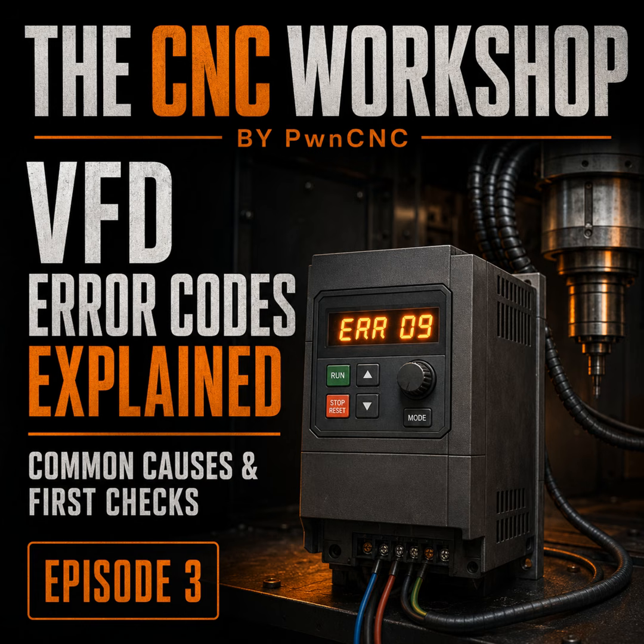Daniel, if listeners remember just 3 things from this episode, what should they be? First, an error code is a clue, not a complete diagnosis. Second, if the spindle stops during a cut, stop the CNC and do not repeatedly reset the VFD. Third, preserve the evidence, photograph the display, record what the machine was doing, and inspect the system safely before anything gets rebooted or changed. That alone should prevent a lot of damaged tools, mystery replacement parts, and support emails that begin with, "It did a thing."